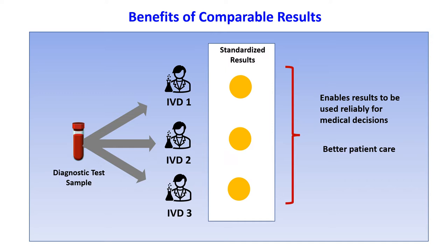To achieve comparable results, all measurement procedures must measure the same quantity. In addition, the calibration of all measurement procedures should be standardized or traceable to a common reference system consisting of reference methods and materials.